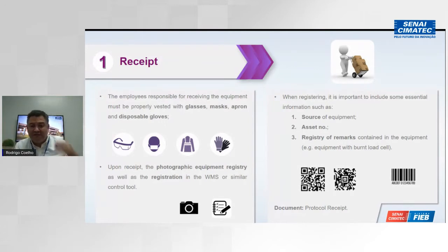And then when the machine is arriving to us, you need to register, doing some pictures, putting some adhesives, so that I can do the traceability of this equipment anytime, so that I know which kind of equipment this is, where it belongs, and what is the historical case of this equipment. I need also to assign a number to this equipment so that I can control it later in my KPIs. So I need to check the statistics of my maintenance, to maybe improve some parts or some labs, in order to have a more and more lean process in my maintenance, and in the end I can ensure that more equipment will be repaired in this process.